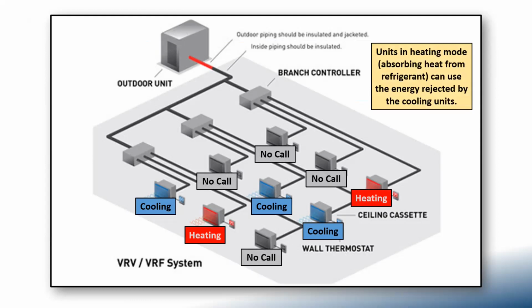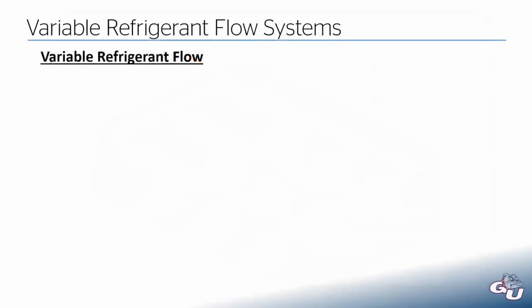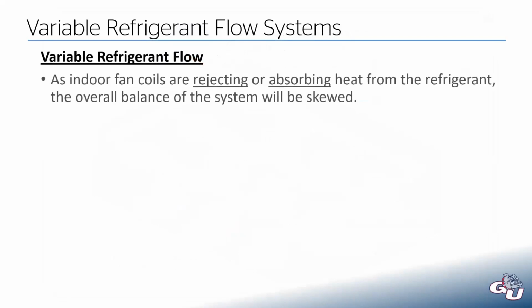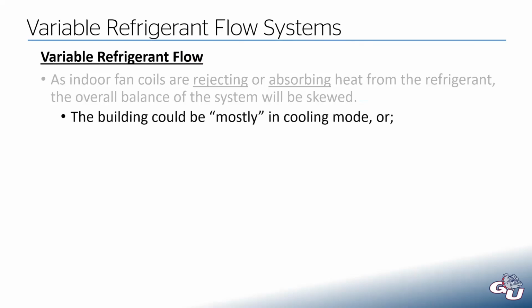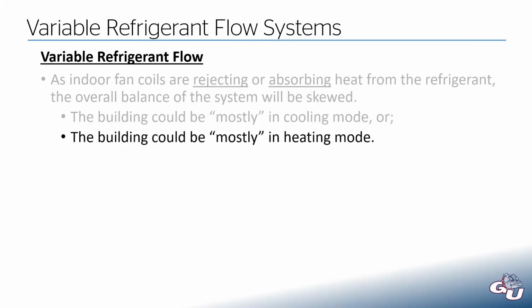So on a fundamental level, that's why this type of system is so efficient, or at least can be very efficient. And so with our indoor fan coils, some are rejecting heat, some are absorbing heat. There is going to be at any given time some balance of the system, and there's going to be a skewedness to what's the overall system need. So the building could be mostly in a cooling mode. So most of the fan coils, or maybe even all of the fan coils, are in cooling mode, or the building could mostly be in heating mode.